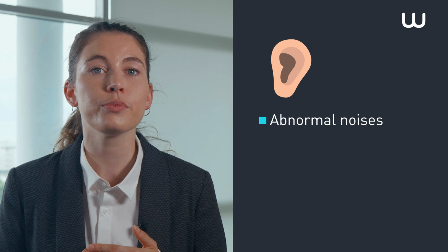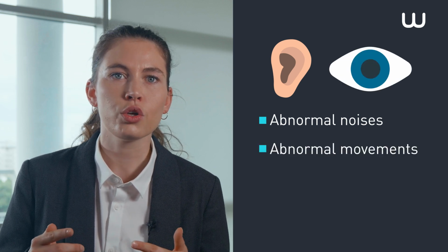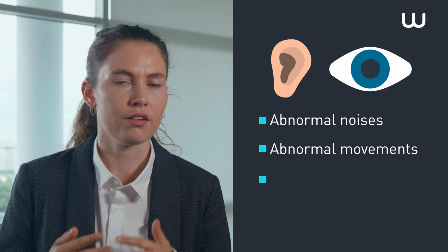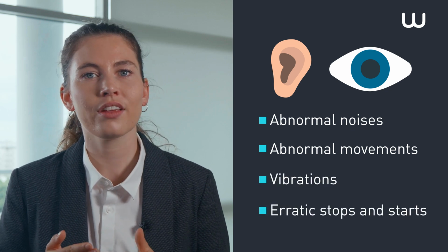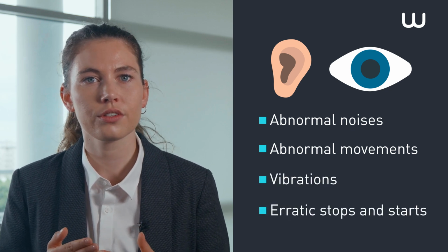Then, generally observing equipment could enable anomalies to be notified, for example, abnormal noises coming from pumps or agitators, abnormal movements such as a swinging agitator, vibrations, erratic stops and starts.